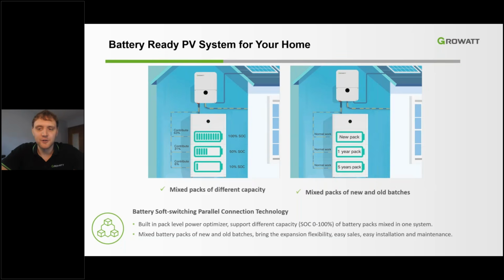So to dive a little bit into the modular energy optimization function, when the battery is charging, the power module intelligently determines the state of health and the state of charge of each battery pack and delivers the optimal charging power to each. The power module will never overcharge an old battery pack, which allows for more battery packs to be added to the system over the course of its operation. During discharge, the power module intelligently controls the rate of discharge from each battery pack to evenly discharge based on state of health and state of charge of each. Innovative features like these are truly showing why Growatt is the best choice for your energy storage solutions.